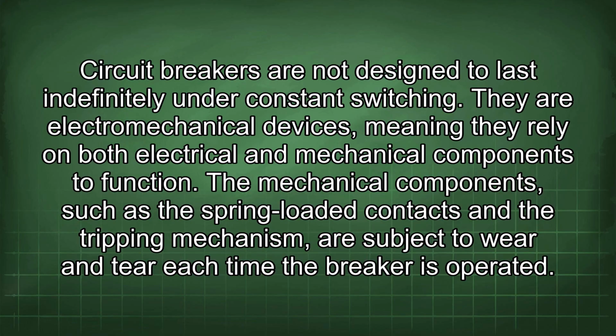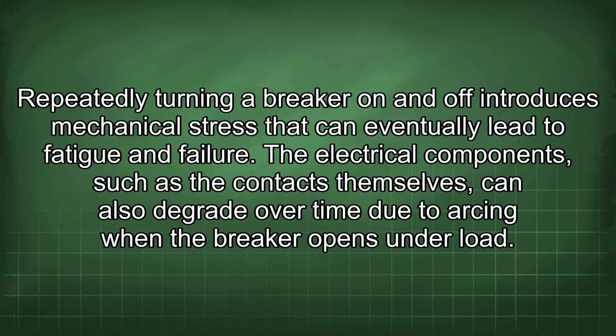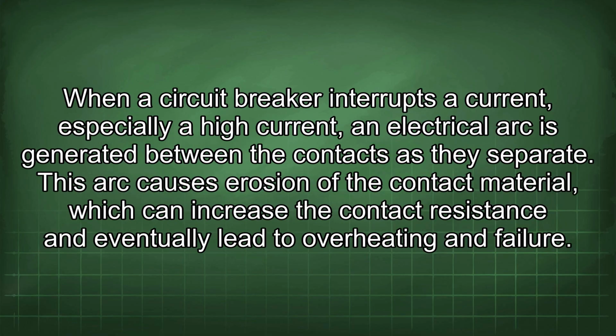The mechanical components, such as the spring-loaded contacts and the tripping mechanism, are subject to wear and tear each time the breaker is operated. Repeatedly turning a breaker on and off introduces mechanical stress that can eventually lead to fatigue and failure. The electrical components, such as the contacts themselves, can also degrade over time due to arcing when the breaker opens under load. When a circuit breaker interrupts a current, especially a high current, an electrical arc is generated between the contacts as they separate.